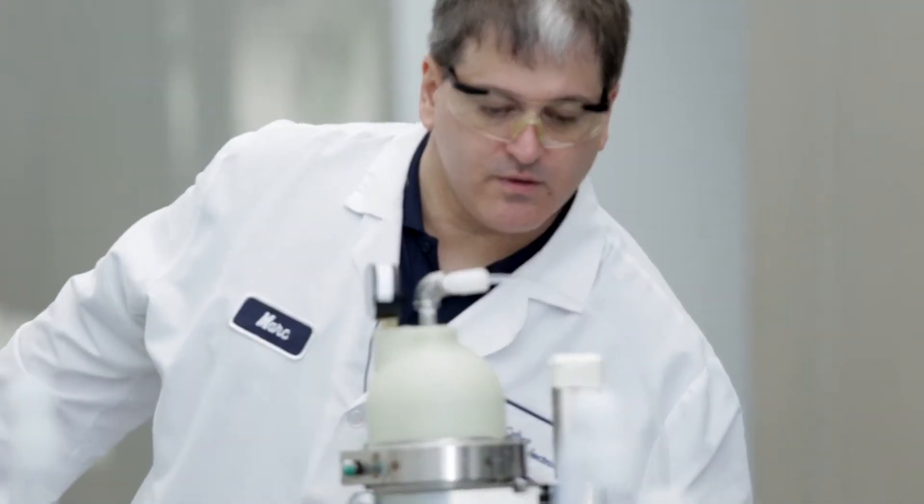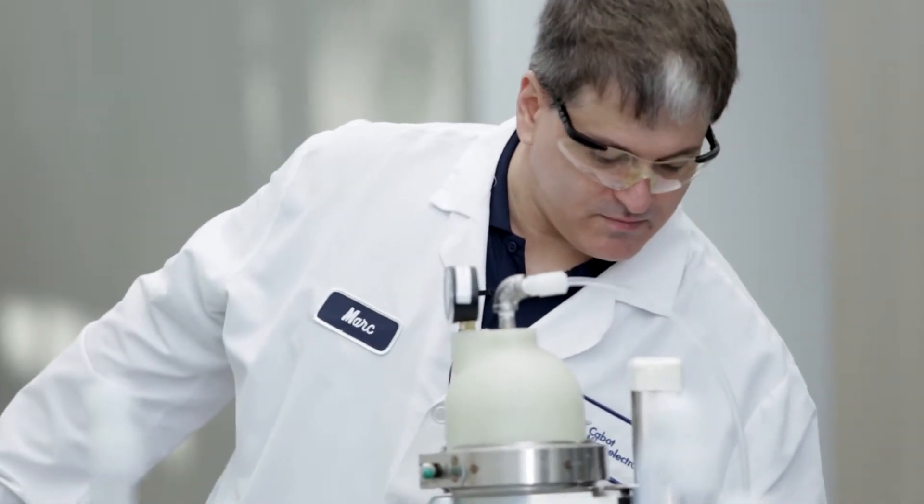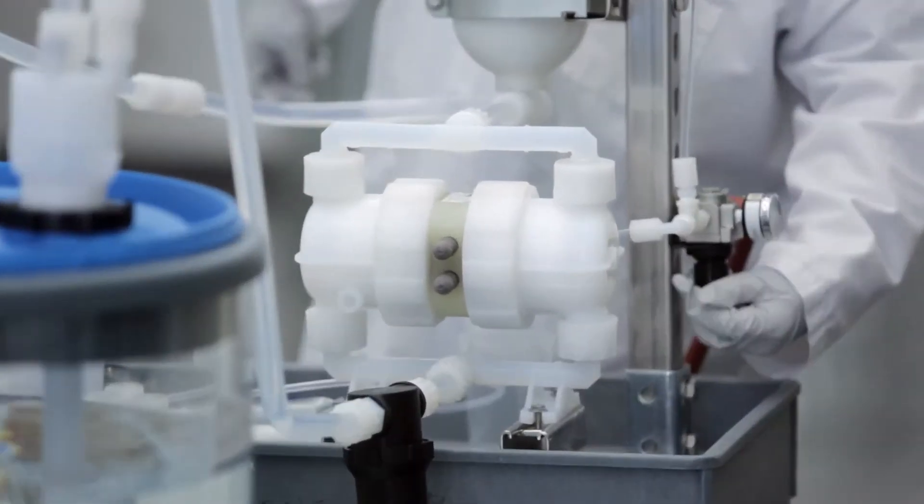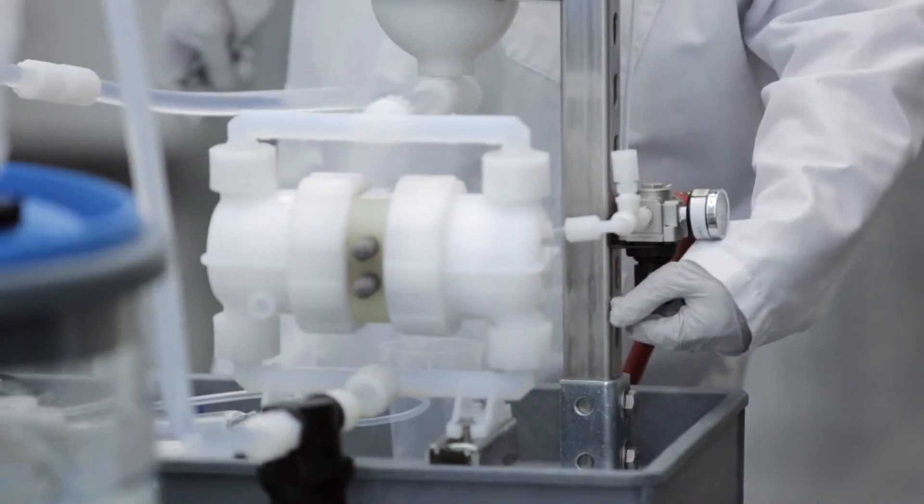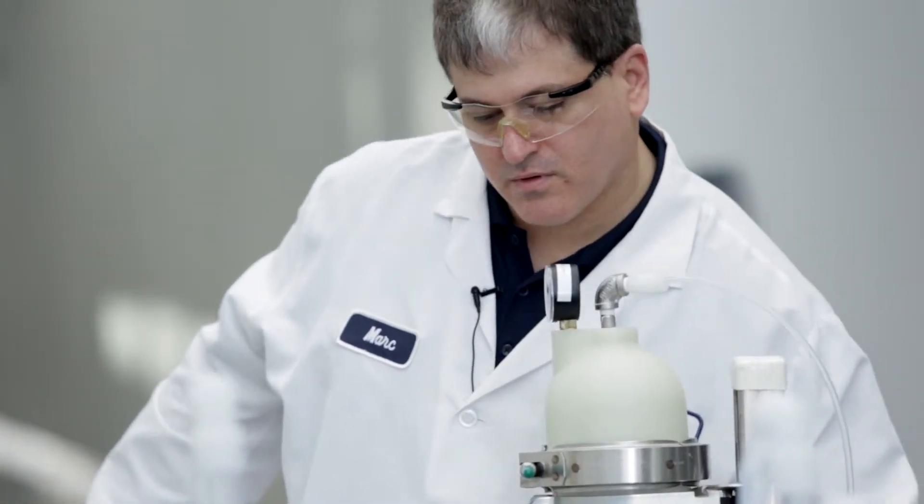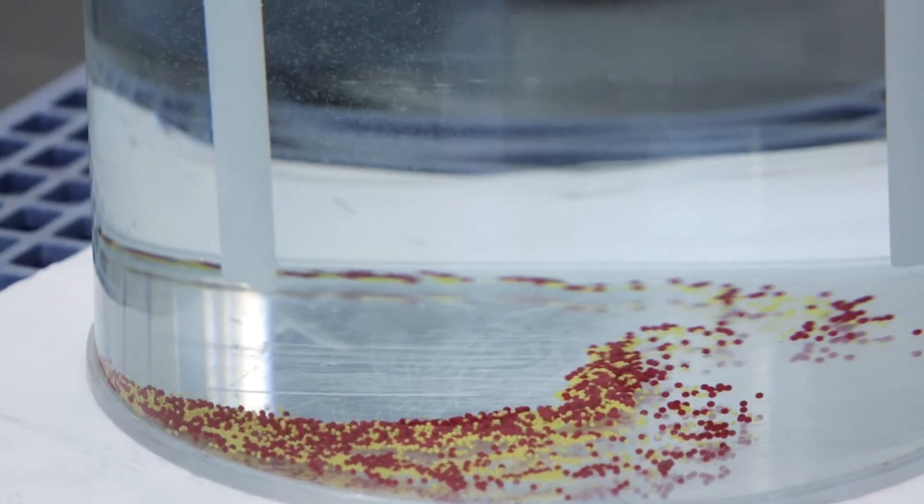And when we start off pump recirculation, as you can see, at the bottom of the drum, the feed and return dip tubes are not effective in moving the heavily settled solids that are on the bottom of the drum.